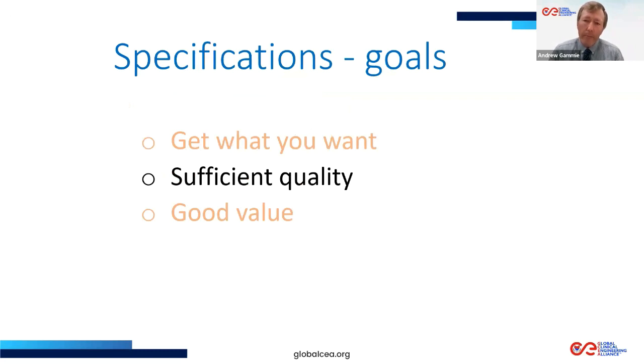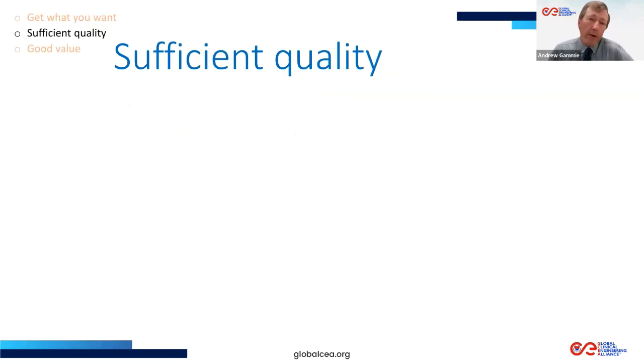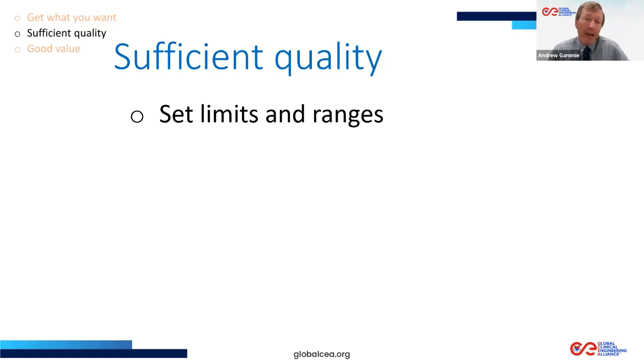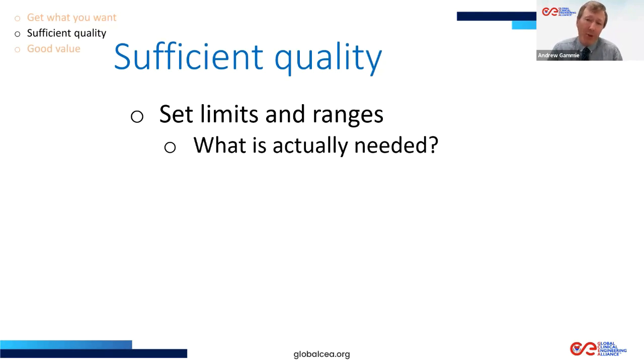What about quality? Sufficient quality. Interesting, I use that word, sufficient, because we mustn't over-specify or under-specify. You don't want to have a device that is the top of the range if it's going to be day-to-day use in your district hospital, because it doesn't need the really fancy machine. It needs something that is robust, good for the environment, and does a job well. So you set your limits and ranges. You say how good it's got to be and what sort of performance it's got to have. What is actually needed is the question you need to ask yourself. And then you are saved from over-specifying.